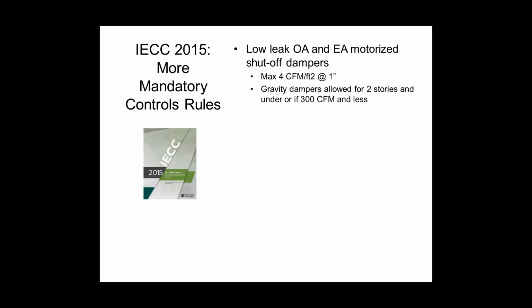So when you're picking a thermostat, pick one that has that output on it. Keep moving along. For the control side of the world, outside and exhaust dampers. You're required to have shutoff dampers, obviously, and now they have to be, quote-unquote, low-leak dampers. Low leak is specifically determined to be 4 CFM per square foot at 1 inch of pressure. So that's what defines a low-leak damper.